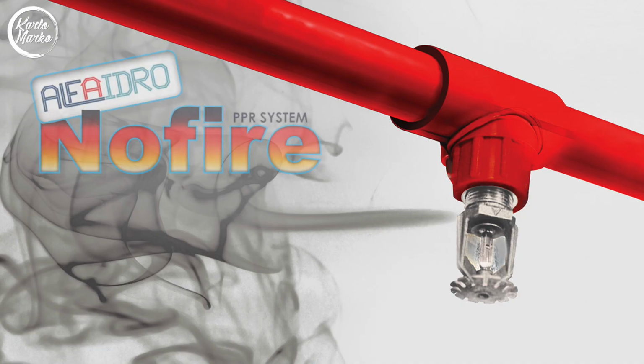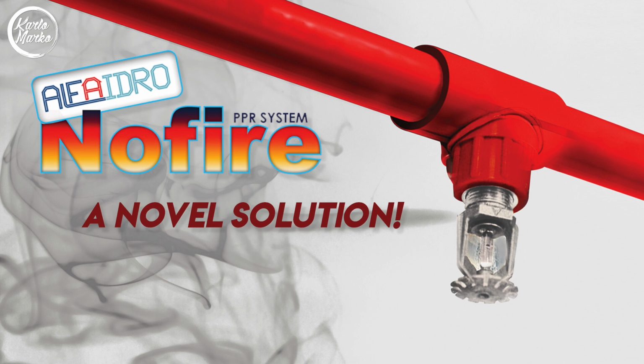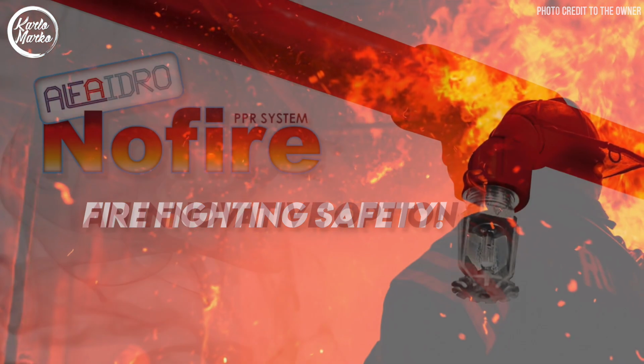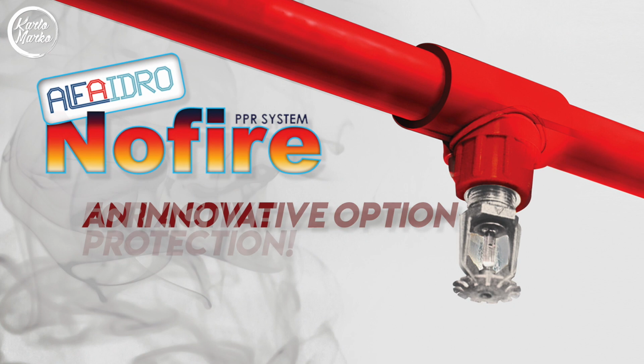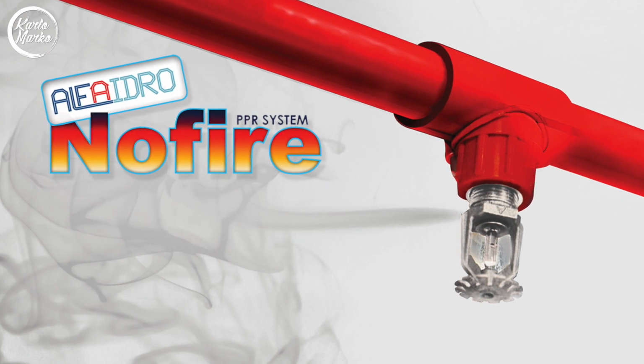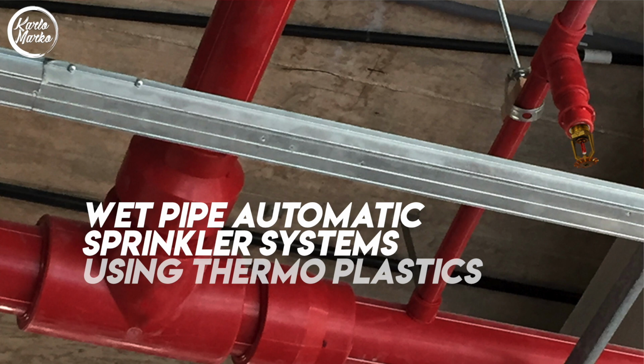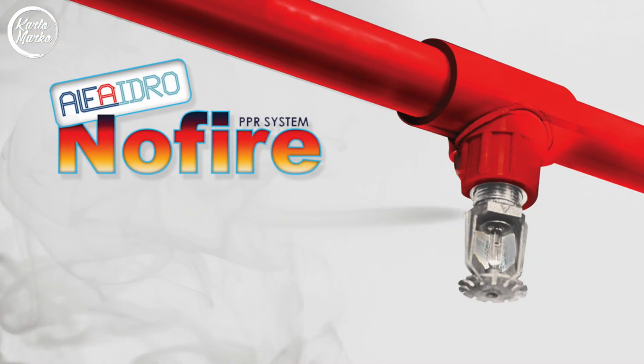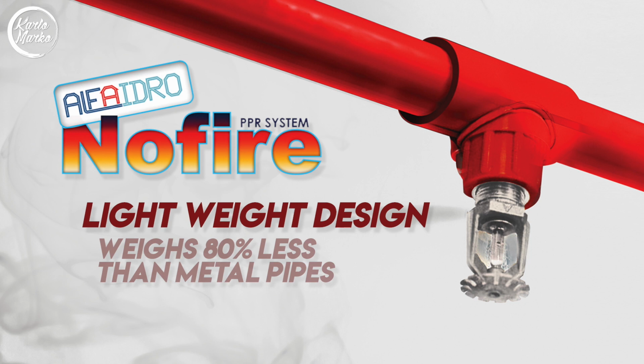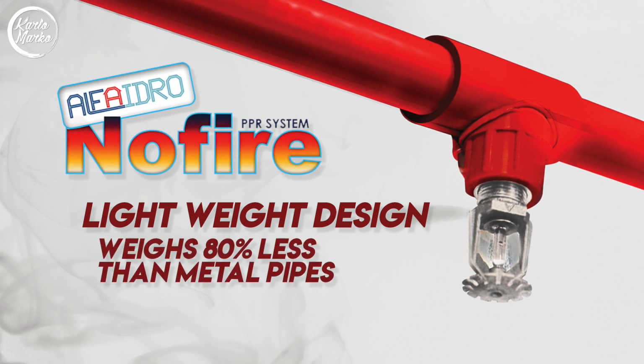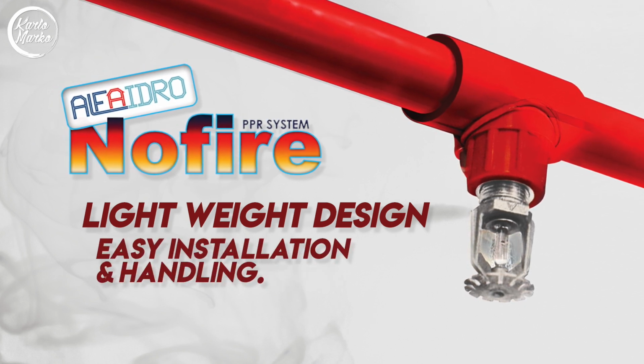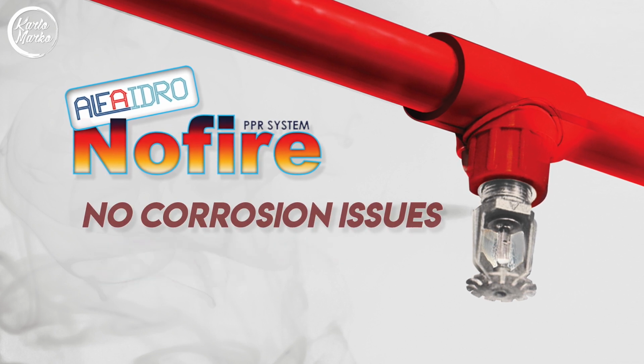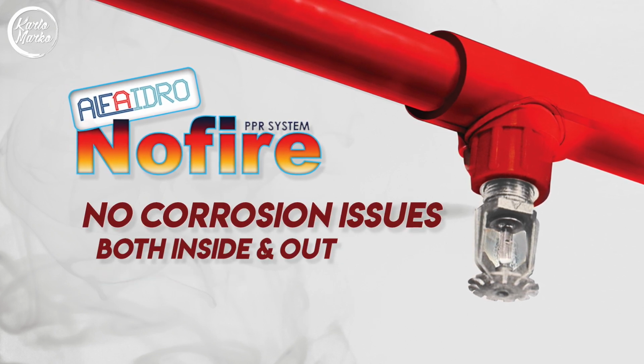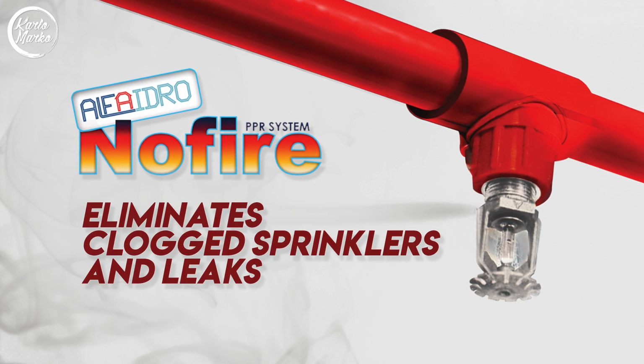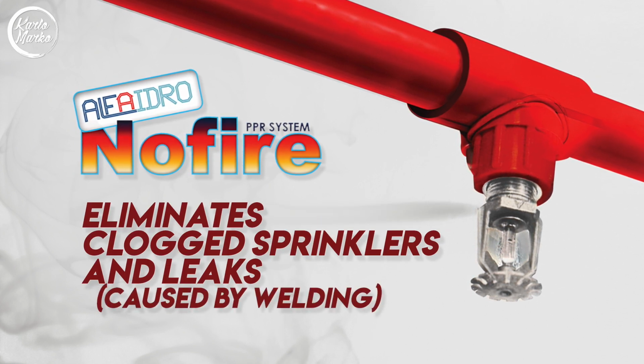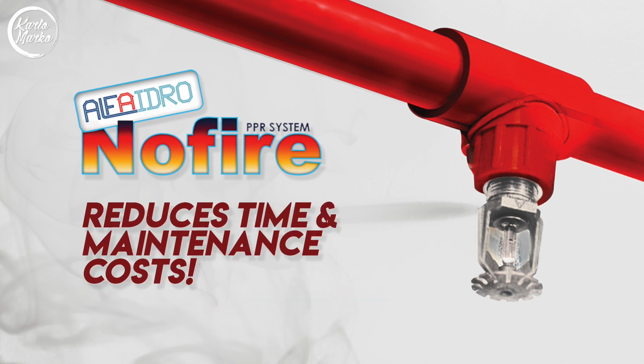Watch this. Alfaidro No Fire is a novel solution in the field of firefighting safety that offers innovative options from traditional metal systems for active protection, particularly in wet pipe automatic sprinkler systems using thermoplastics. Its notable features include its lightweight design, weighing up to 80% less than metal pipes. This gives ease of installation and handling. And to add to that, it eliminates the issues of corrosion both inside and outside the pipe. It also eliminates the issues of clogged sprinklers and leaks caused by welding. Therefore, it reduces time and maintenance costs.